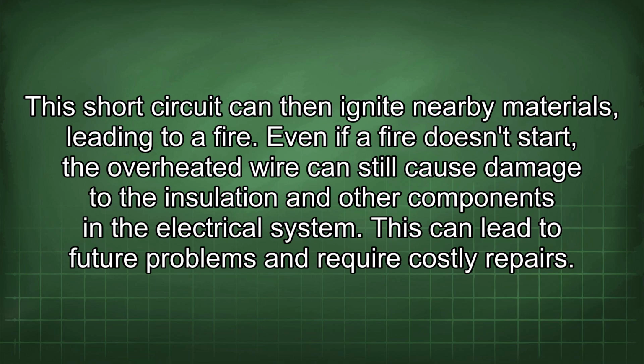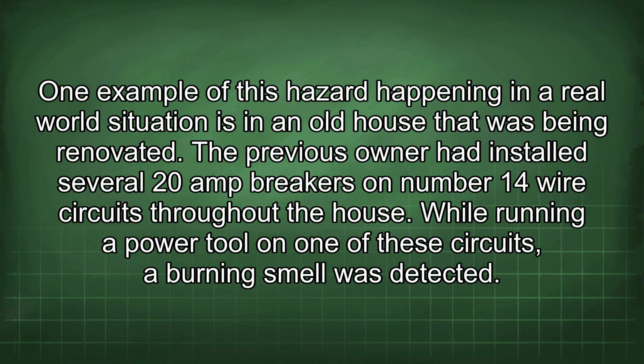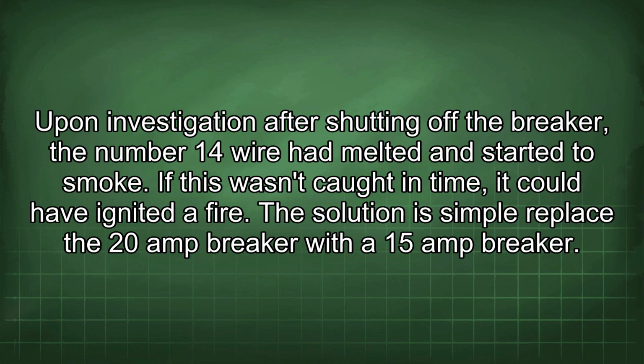Even if a fire doesn't start, the overheated wire can still cause damage to the insulation and other components in the electrical system. This can lead to future problems and require costly repairs. One example of this hazard happening in a real-world situation is in an old house that was being renovated. The previous owner had installed several 20 amp breakers on number 14 wire circuits throughout the house. While running a power tool on one of these circuits, a burning smell was detected. Upon investigation, after shutting off the breaker, the number 14 wire had melted and started to smoke. If this wasn't caught in time, it could have ignited a fire.